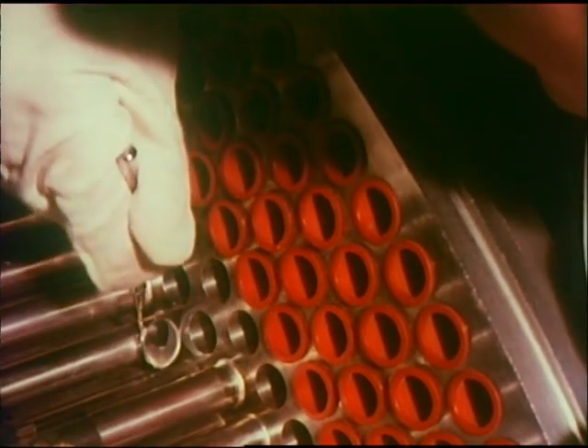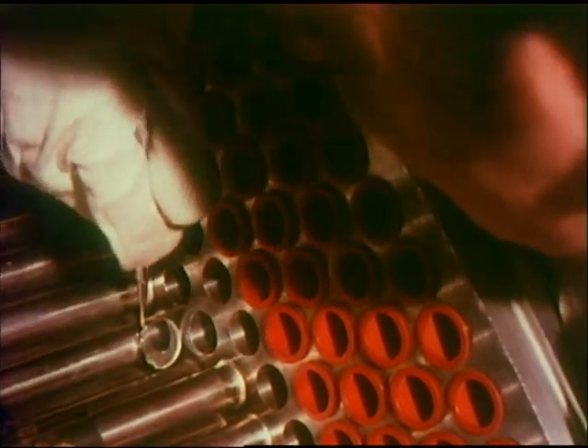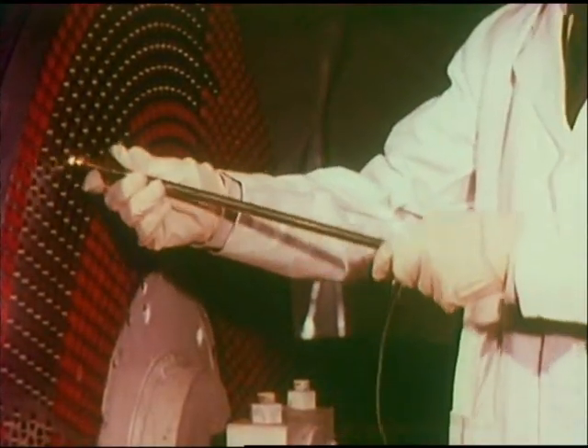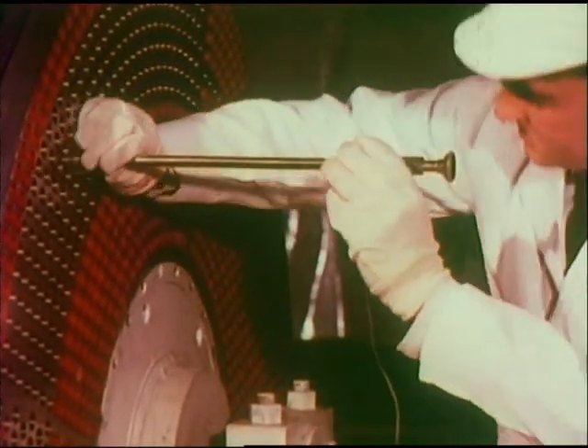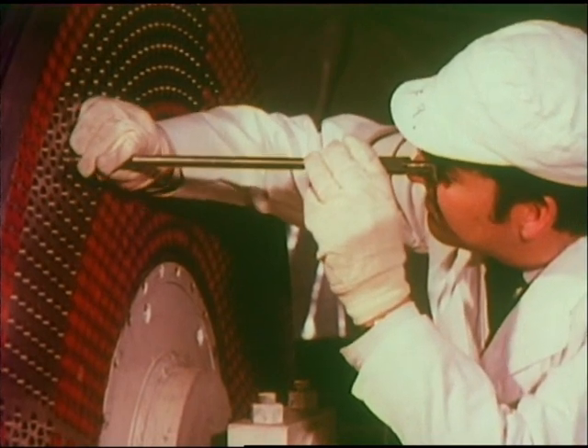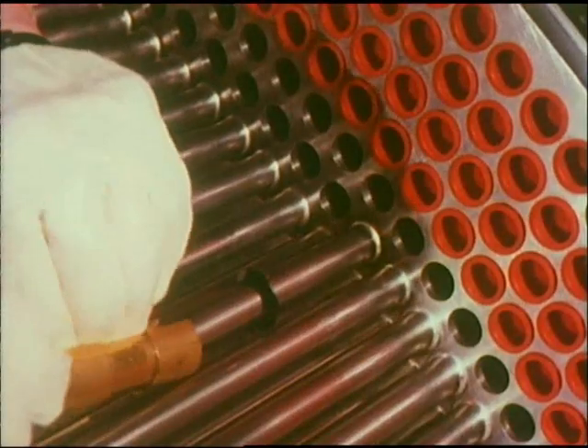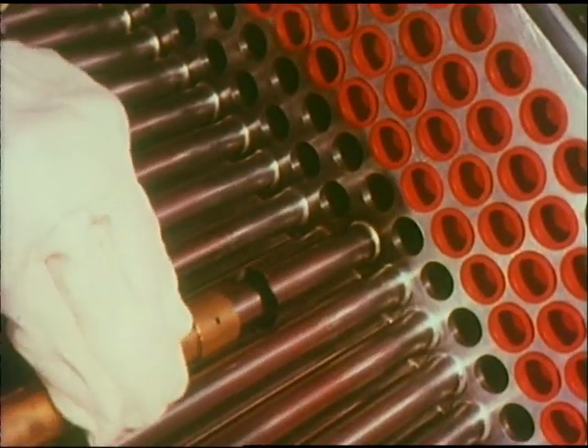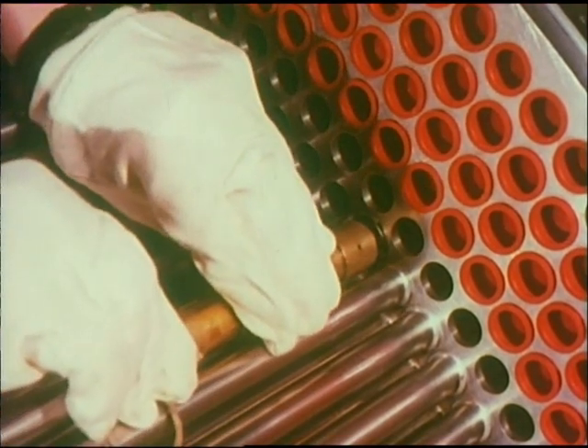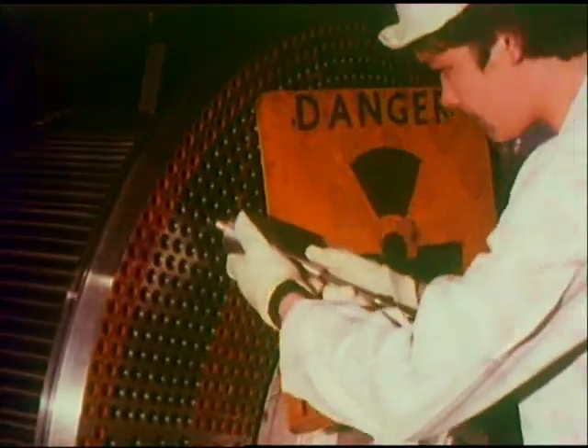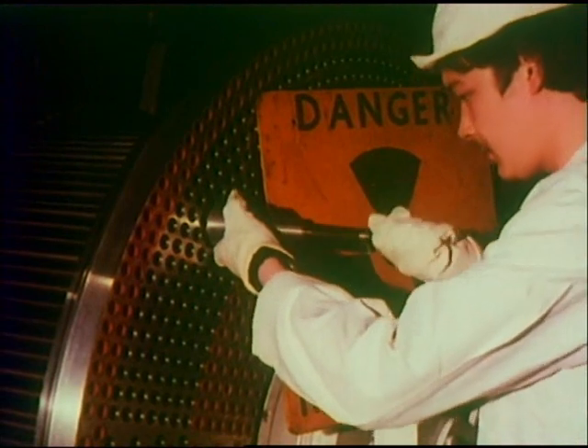Correct weld profile was of the greatest importance. All welds were examined on the inside of each tube with an optical instrument. Later, they were radiographed, the film being attached to the outside of the tube. The gamma ray source to expose the film was then inserted inside the tube.